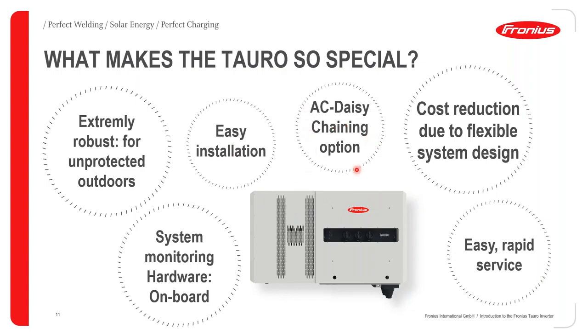With the Tauro, we'll also have the capability to do AC to AC chaining. Basically what that means is that you can connect the AC out of one Tauro to the AC in of the Tauro next to it, up to 200 kilowatts. The advantage there is you can now cut down on the amount of AC cabling you will need for your system. You also have a cost reduction, and this is due to extremely high flexible design. And lastly, we also have easy rapid service. With the Fronius Tauro, you can do power stack replacement on site. So if the power stack does go, you can just request a new one from Fronius and do the replacement on site. You do not need to send the inverter back to Fronius and wait for a few weeks. There's nothing of that sort. You will get instant rapid service.